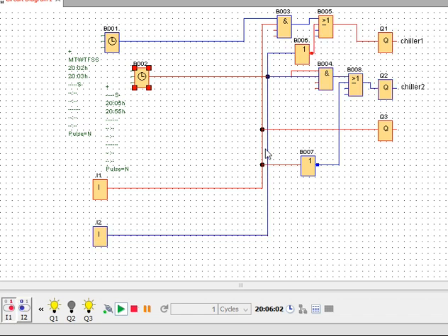So once this is going off, you can see the same time this one is going off, and the next chiller Q1 received the command. It's switched off from schedule, as you can see from here, but once it received command when this chiller is going in fault Q2, so this one is going on. So in same like now it's receiving command from here, it's a fault signal.